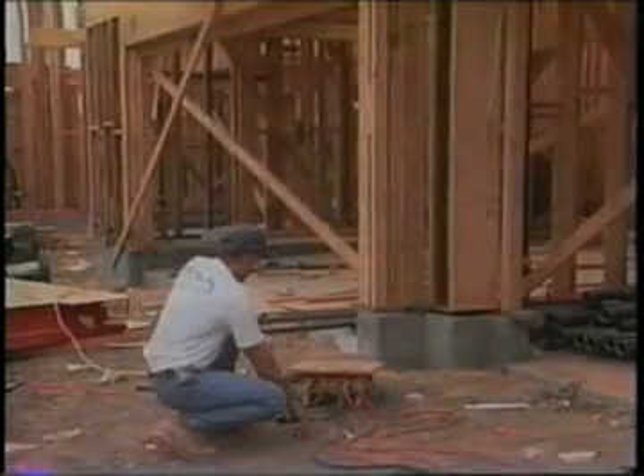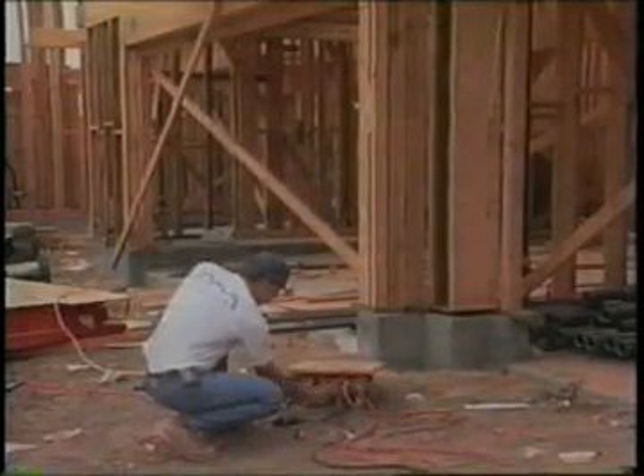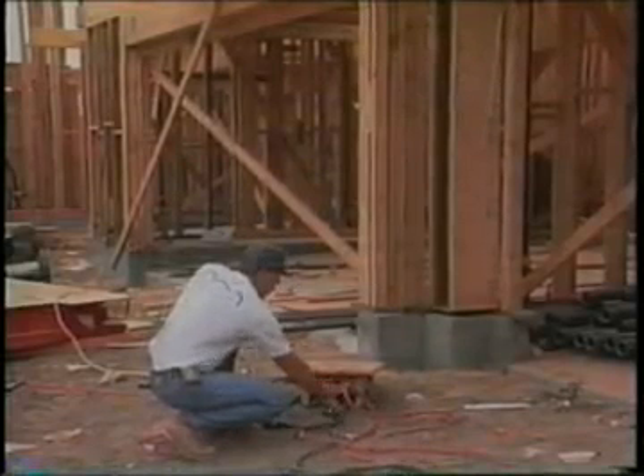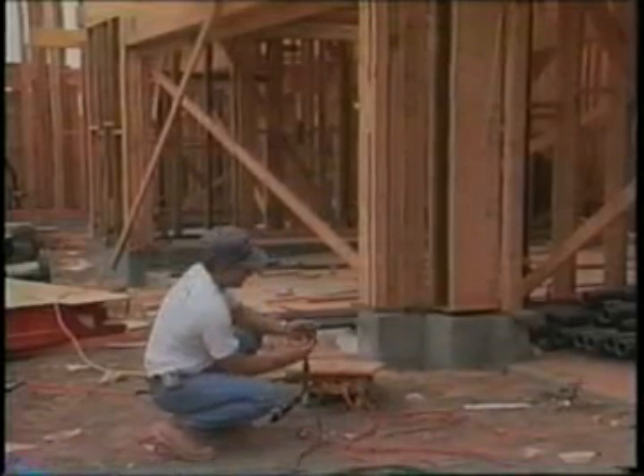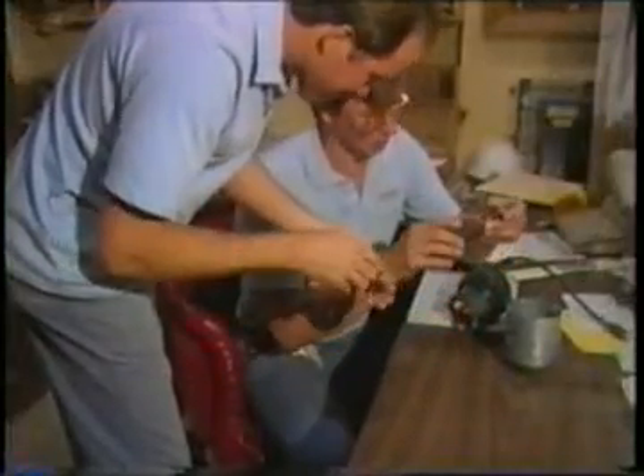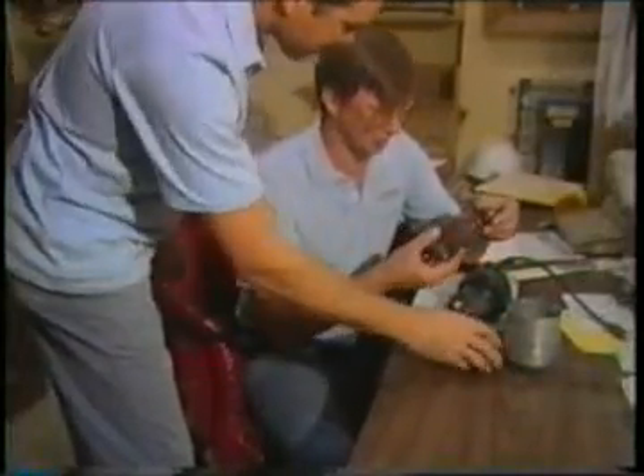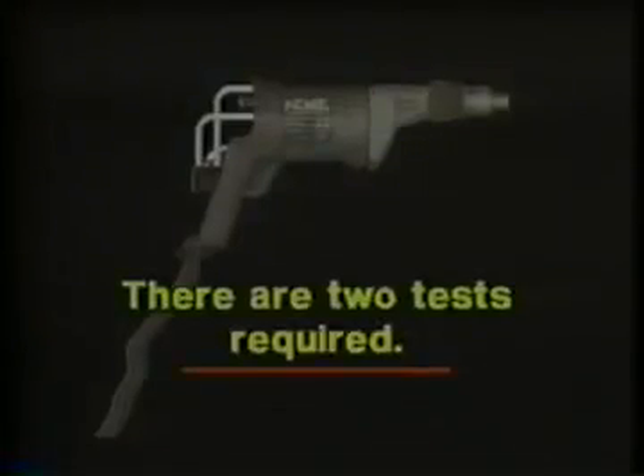Electrical equipment noted in the Assured Equipment Grounding Conductor program must be visually inspected for damage or defects before each day's use. Any damaged or defective equipment must not be used until it's replaced or repaired. There are 2 tests required. One is a continuity test to ensure that the equipment grounding conductor is electrically continuous. This test may be performed using a simple continuity tester, such as a lamp and a battery, a bell and a battery, an ohm meter, or a receptacle tester.